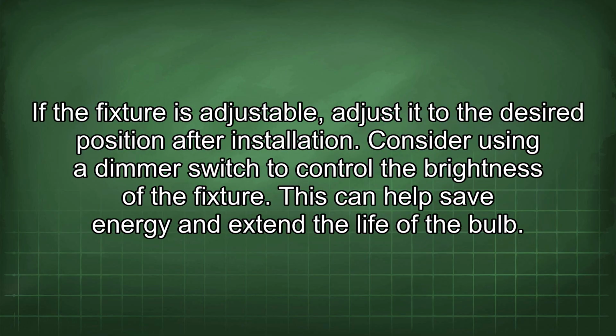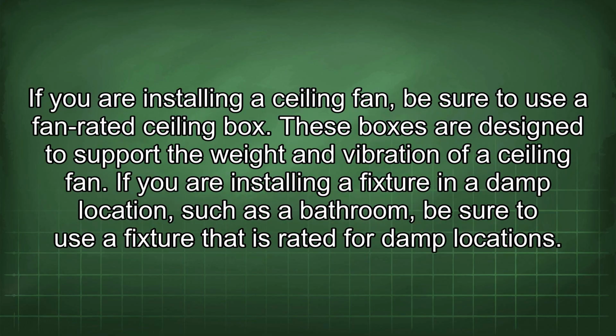If the fixture is adjustable, adjust it to the desired position after installation. Consider using a dimmer switch to control the brightness of the fixture. This can help save energy and extend the life of the bulb. If you are installing a ceiling fan, be sure to use a fan-rated ceiling box. These boxes are designed to support the weight and vibration of a ceiling fan.